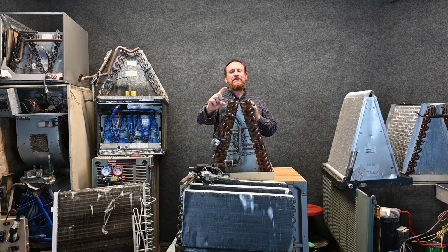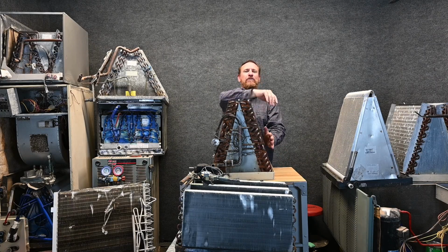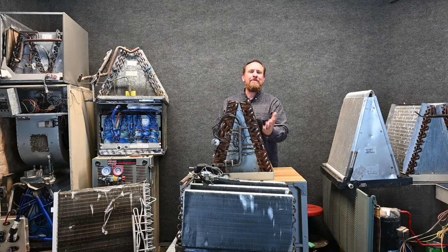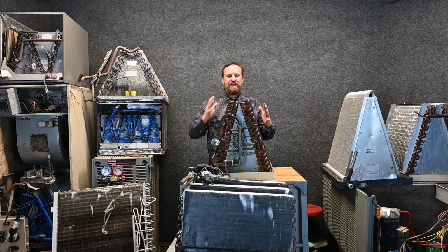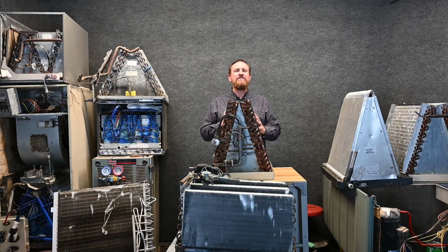And if I know how much vapor I have, I can also see how much liquid, or liquid vapor mixture, I have inside my evaporator coil. So by measuring the superheat, I can get an idea what's happening with my latent heat, my saturation liquid vapor mixture. So this evaporator coil on the refrigerant side simply boils it from a liquid to vapor and then superheats it above that saturation temperature.